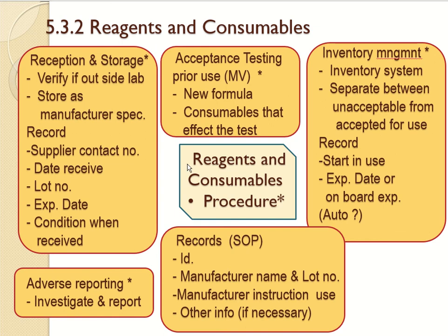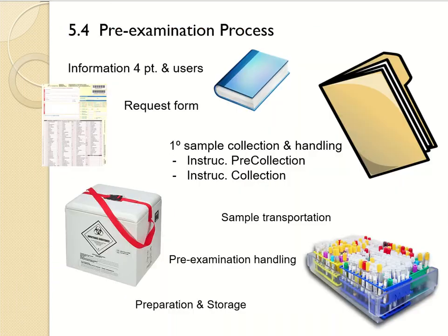And the reagent and consumable shall have records, which are covered in the SOP and the operating procedure, consisting of identification of the reagent and consumable, manufacturer name and lot number, manufacturer instructions for use, and any other info if necessary. Now we go to the pre-examination process under clause 5.4.